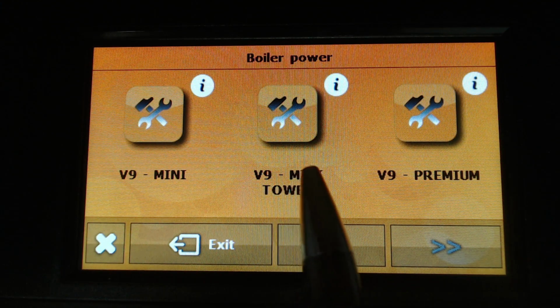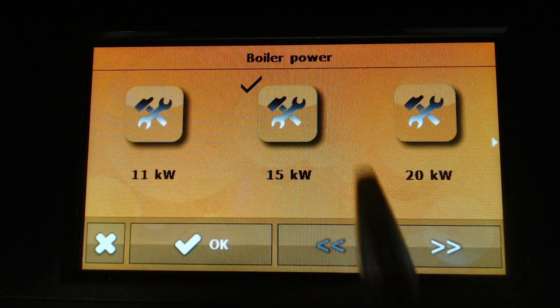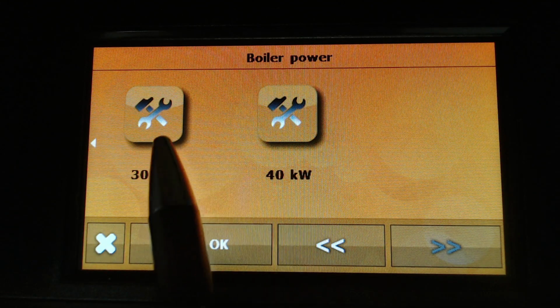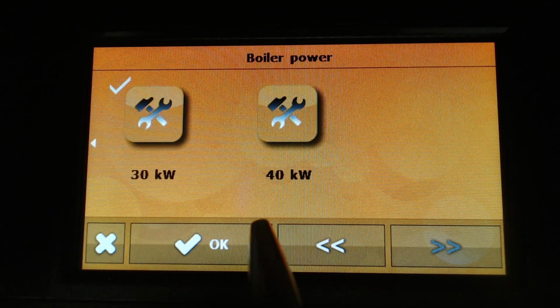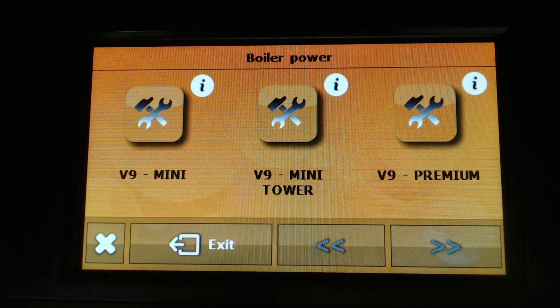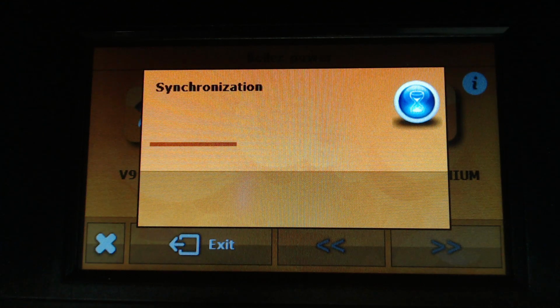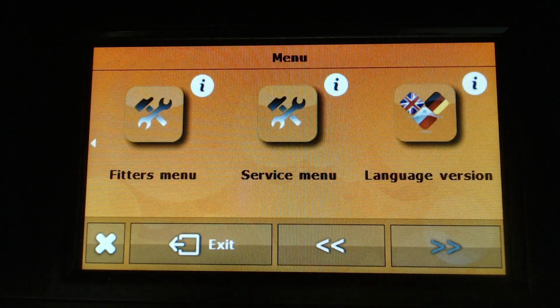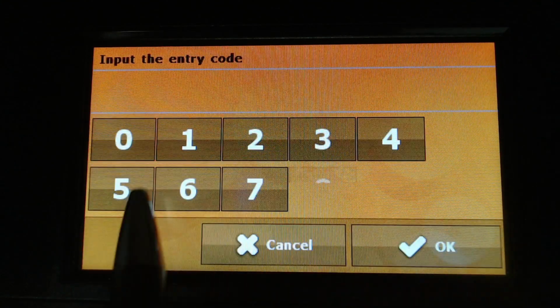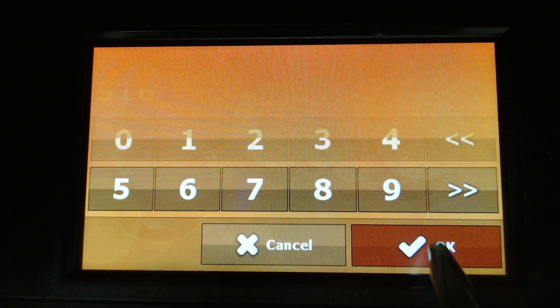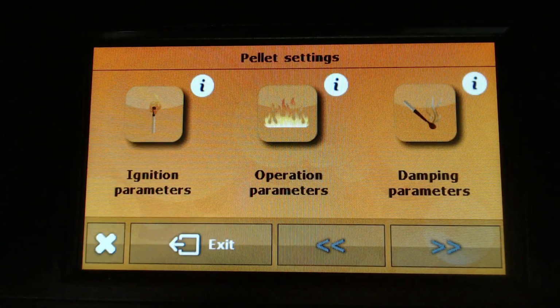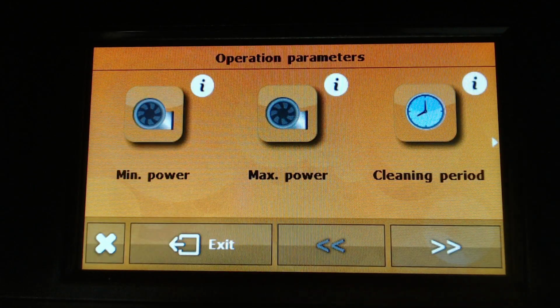So in our case, let's say we have a Mini Tower, and let's say we have 30 kilowatt. Okay, we have Biopal Mini Tower 30 kilowatt. Exit, and now it will save factory settings only for this boiler, for the 30 kilowatt V9 Mini Tower version. So it's up to you to select the power and type of the boiler properly. And now in the service menu, if we access it with the standard password, we have pellet settings, and inside the pellet settings we have operational parameters, and then min power and max power. Here we have a different setup for feeder operation and fan speed.